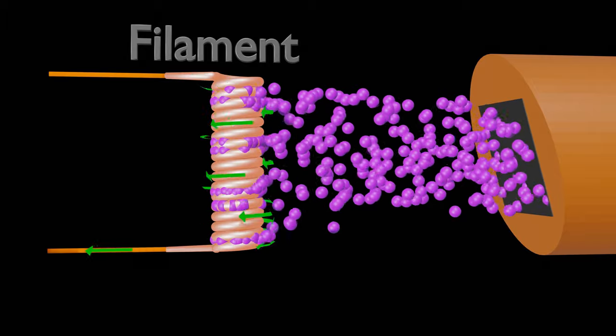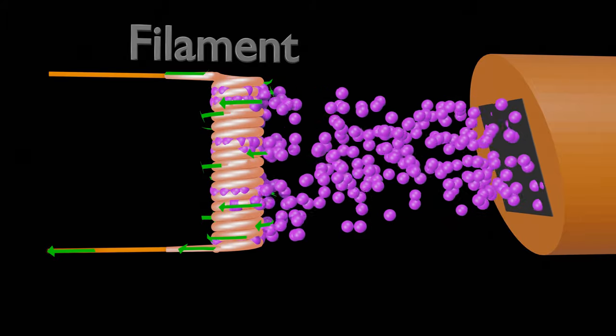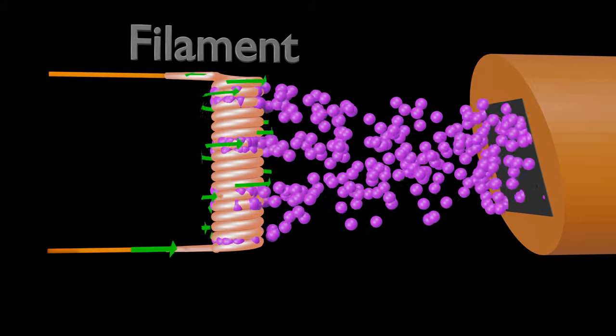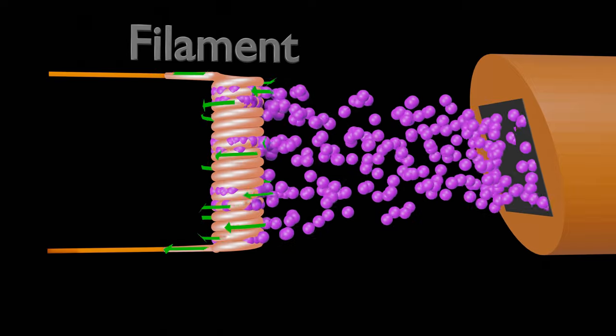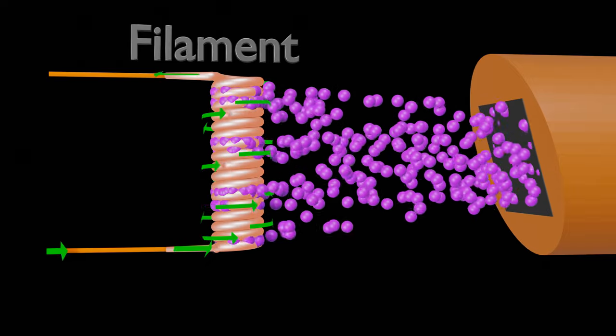If one increases filament current, more electrons will flow inside the X-ray tube, and more will be the tube current. Let's discuss filament circuit in details.